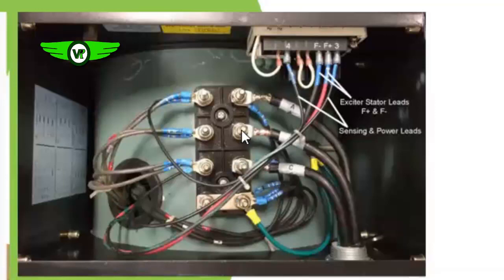So black probe neutral, your red probe to line 3, that will give you 220 volts. To line 2 will give you 220 volts. To line 1 will give you 220 volts. So to this midpoint, it will give you 110 volts.